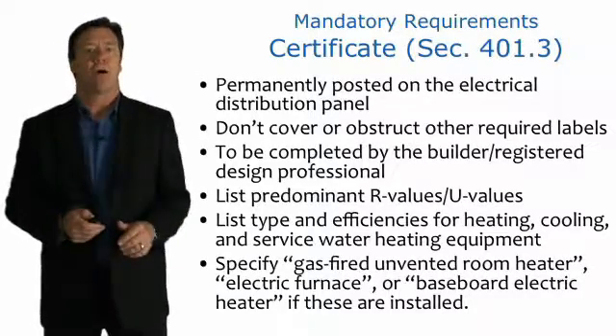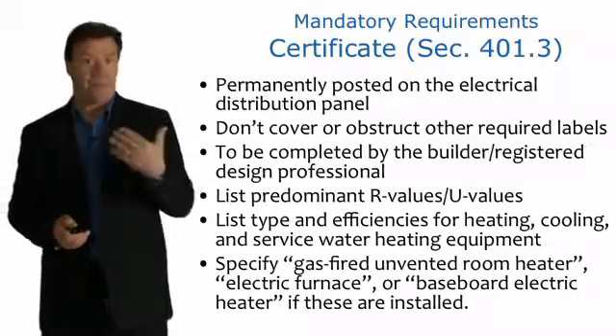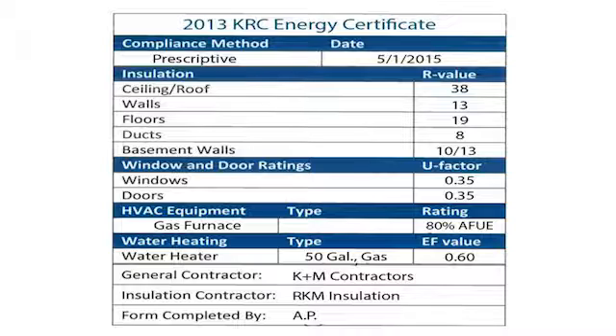The certificate lists predominant R-values and U-values, the types and efficiencies of heating, cooling, and water heating equipment, and specifies whether a gas-fired unvented room heater, electric furnace, or baseboard electric heater is installed. Here's an example of what one of these certificates looks like for Kentucky. At the top, the compliance method was prescriptive, and then you have the R-values listed. The inspector simply looks at the 402.1 chart and then this certificate to verify that insulation in the ceiling, walls, floors, and roof meets the standard. It also tells the type of HVAC equipment and gives the U-factor of windows and doors.